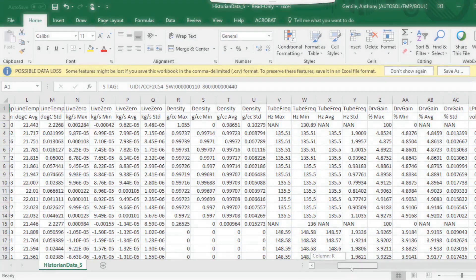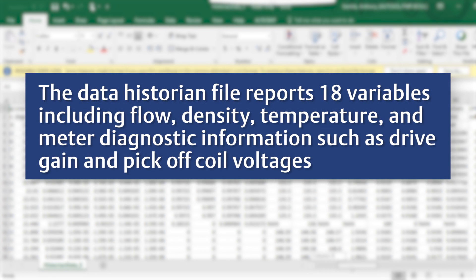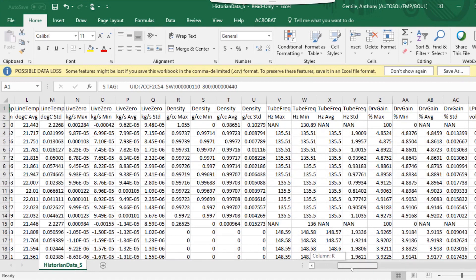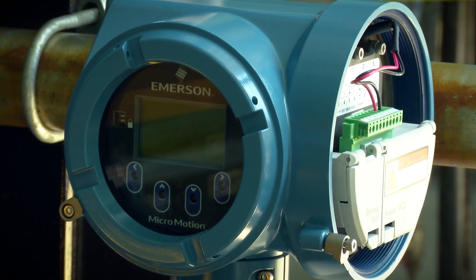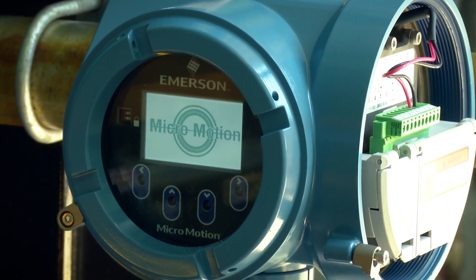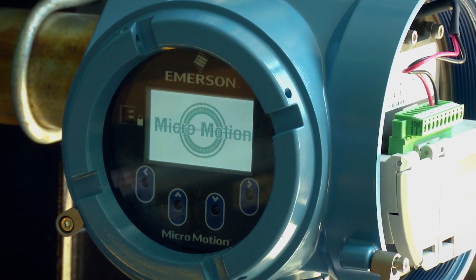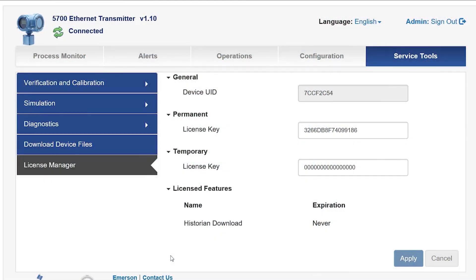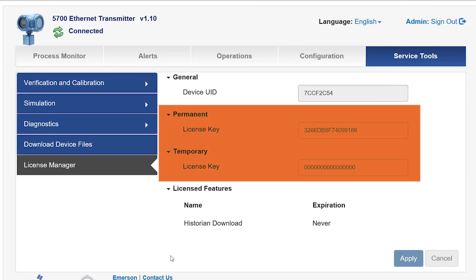The data historian file reports 18 variables including flow, density, temperature, and meter diagnostic information such as drive gain and pick-off coil voltages. The historian data logging begins automatically when the user powers the transmitter, ensuring the user does not miss critical data points for troubleshooting purposes. The License Manager menu allows the user to view the device's unique identification, current license key, and licensed features. The user can choose to upgrade and add features to the transmitter using this information.